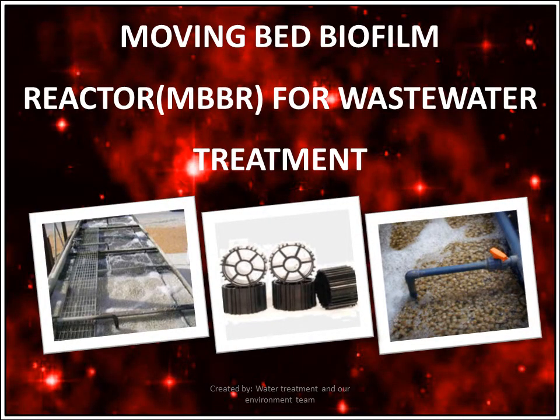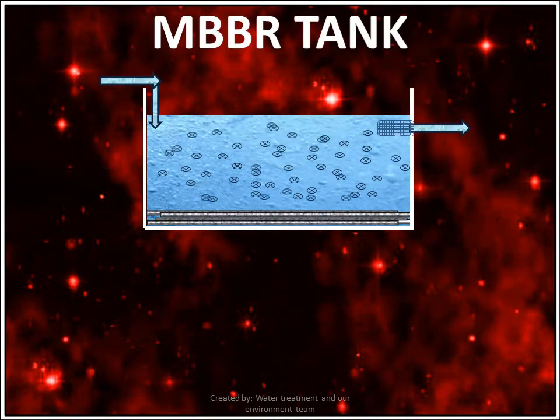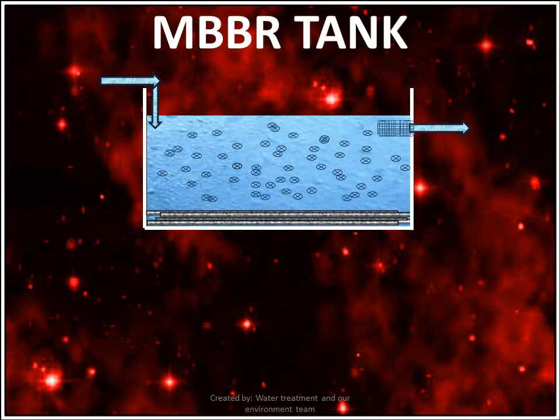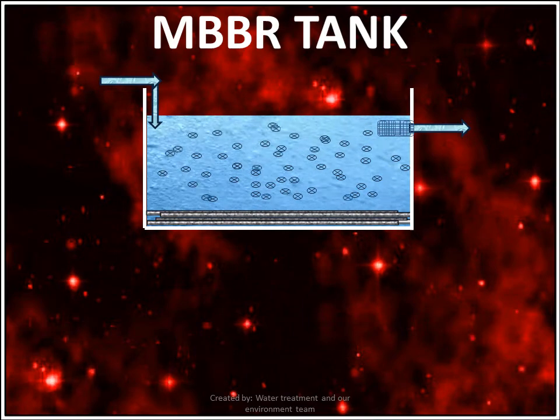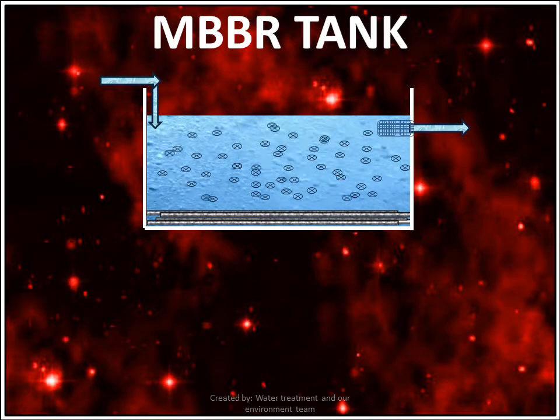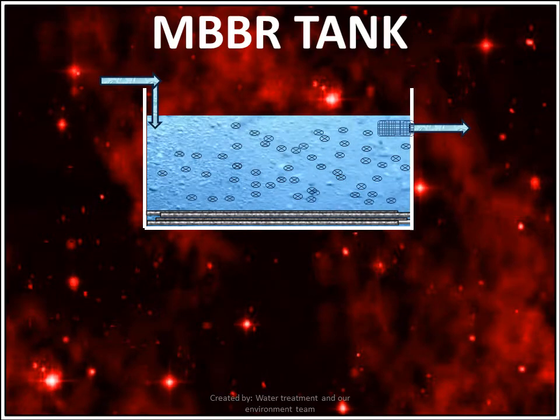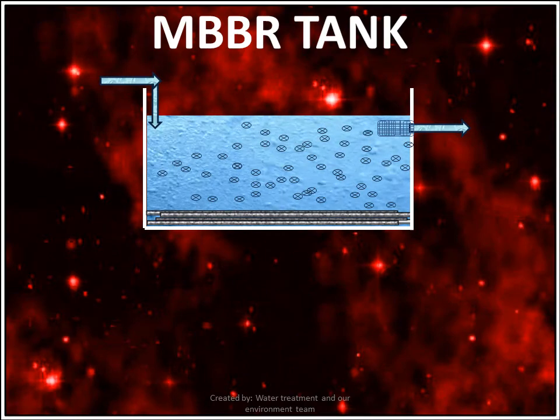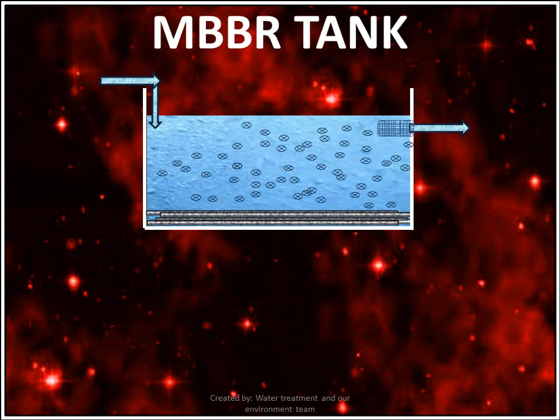Moving bed biofilm reactor, or MBBR, for wastewater treatment. This is the schematic diagram of an MBBR tank. The process consists of adding small cylindrical polyethylene carrier elements which have a specific gravity of 0.96 grams per centimeter cube in aerated or non-aerated basins to support biofilm growth. The small cylinders are about 10 mm in diameter and 7 mm in height, with a cross inside the cylinder and longitudinal fins on the outside.